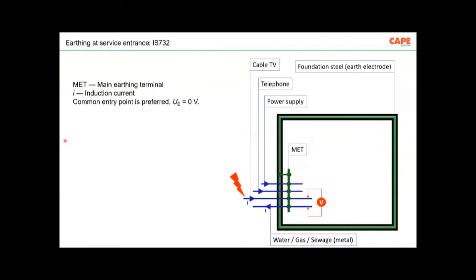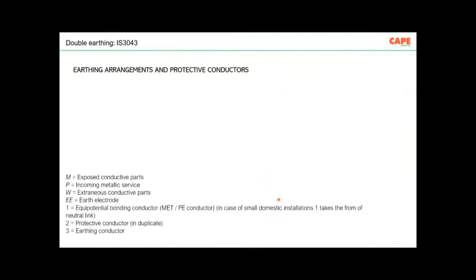Number three, this protective equipotential bonding also reduces the shock voltage in case of a fault on the high voltage side of the transformer. Imagine you have an HT transformer and there is a fault on the HT side of the transformer. This fault on the HT side sometimes creates a shock hazard inside your building. But this protective equipotential bonding will provide safety against all these three. So there are three purposes for this protective equipotential bonding at the service entrance.